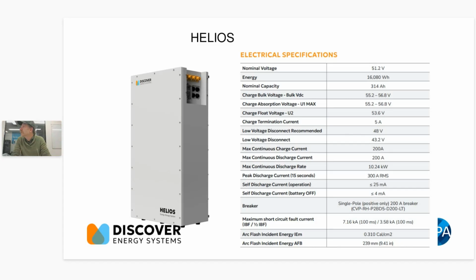Battery terminal on top left and right of battery. Can we daisy chain 3 batteries from terminal to terminal? Or is it best to use 3 sets of cable? So the issue with these is that they're designed by Americans. So they don't have the same rules that we do. It has an integrated 200 amp breaker, but it only breaks 1 pole. So you have to use an external 2-pole breaker for each battery. It's not too much of an issue, especially if you're just putting 1 battery in, because you need one for the inverter anyway.